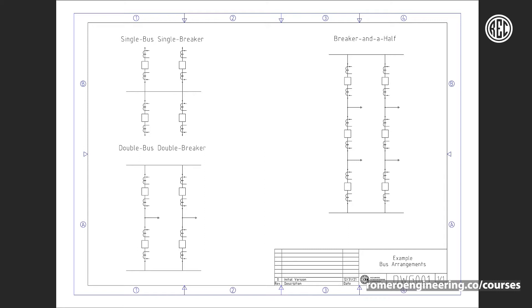Bus faults can cause severe system disturbances because we have multiple sources that will feed the fault. Bus faults typically have very high fault current magnitudes and are therefore very severe in the system. There are many different bus configurations, each with its own pros and cons. In this lecture, we're going to look at three of them: the single bus single breaker (also called a straight bus configuration), the double bus double breaker configuration, and the breaker and a half configuration.